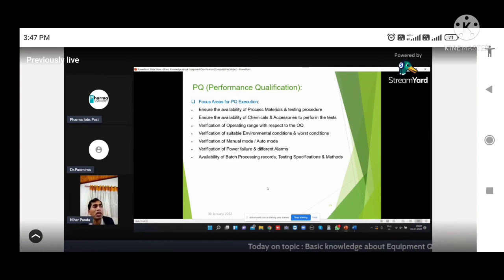Then verification of suitable environmental conditions and worst conditions. What is the feasible environmental condition? What is the suitable environmental condition? And what is the worst condition? You have to check both parameters. What is the optimum one? And if any worst condition is there, whether the equipment is working at the highest temperature with highest moisture, or it is not working at that condition. You have to verify those things during PQ.